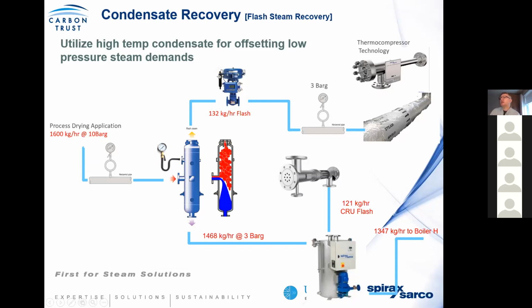You could also take it into what we call an exhaust vapor condenser. What you do is use a cooling medium like process water or boiler makeup water, condensing the flash steam and effectively recovering the energy. So in other words, what this is trying to indicate is that there's no one-fit solution. It's to look at your process, your application, and then see what's the best solution to suit your needs. This is where the benefit of audits comes in, because through the audit, you identify a solution relative to your own applications.